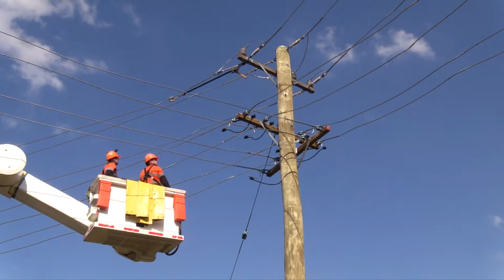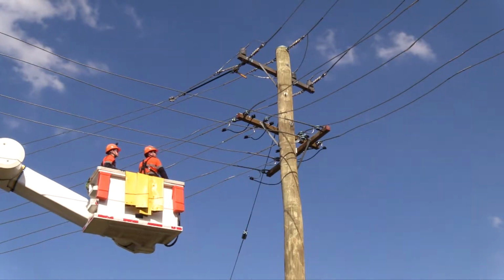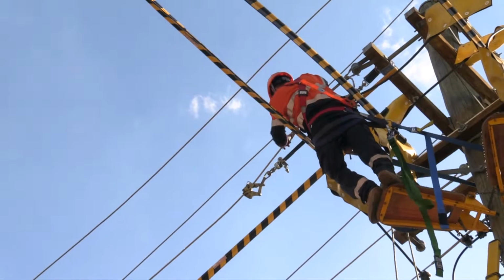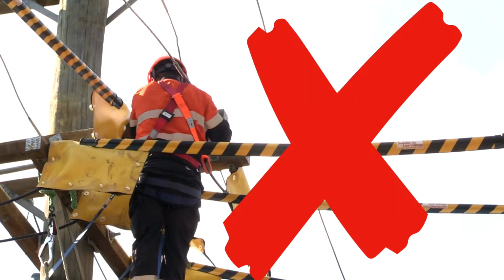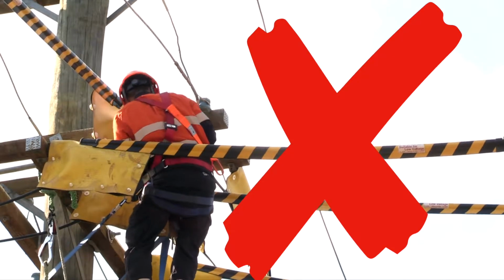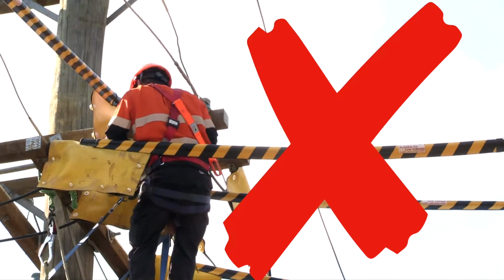Regardless of the authorisation of the workers, there are some live work tasks not permitted on the Endeavour network. On overhead bare multi-phase arrangements, live work on the top circuit or circuits of three-way, four-way, twin circuit or triple circuit constructions is not permitted, except for the installation or removal of bonding conductors or service connections.